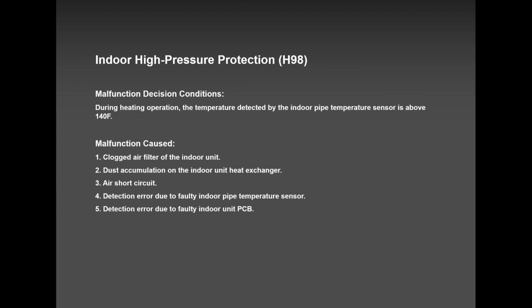H98 is a hidden error. It's a protection error. It will show up when fewer indoor units are running in heat mode. When fewer indoor units are running in heat mode, you will get an H98, but it will not shut down the system. It will store in the EEPROM. The system will keep running unless the unit is super dirty. If the unit is super clogged and super dirty, then yes, the system will shut down and it will start flashing H98.